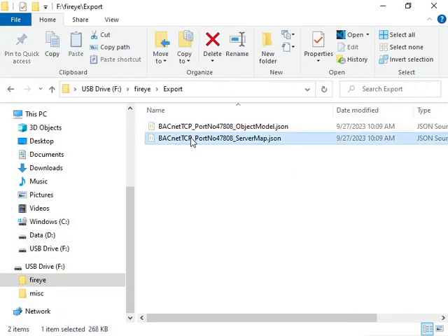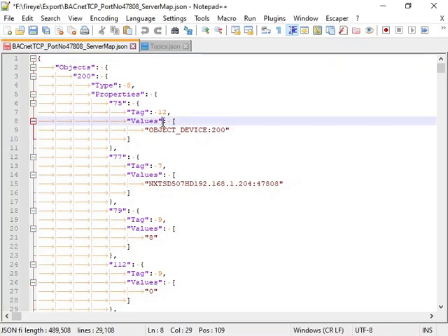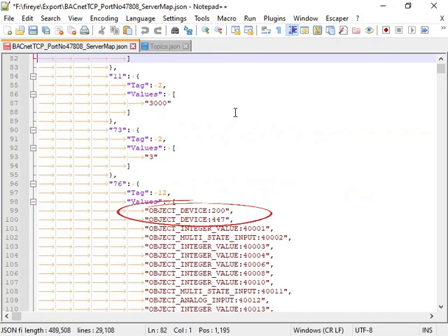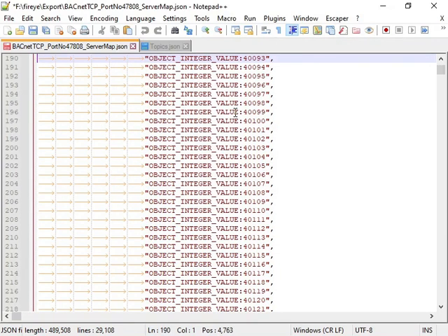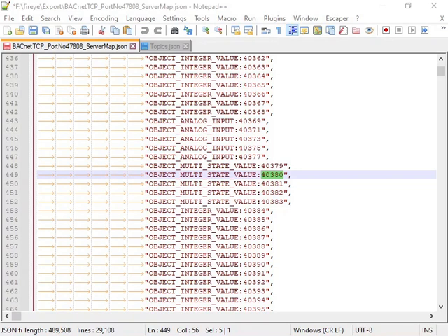The server map details all accessible data points for all devices connected to NXTSD5. You can see the BACnet object IDs of NXTSD5 and Boiler 1 here. Let's scroll down the tag list. We can see Boiler 1's off and on control is located at object ID 40380.